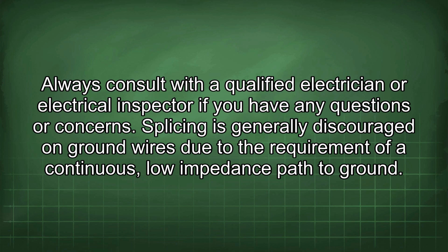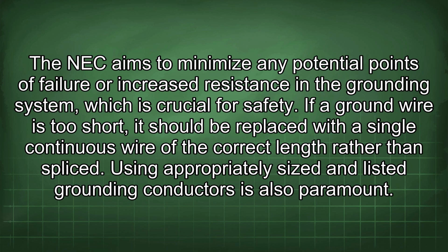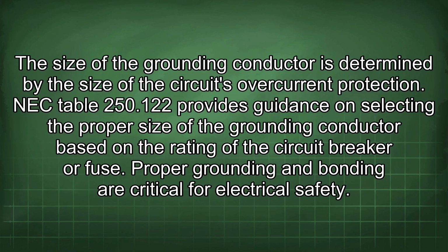Splicing is generally discouraged on ground wires due to the requirement of a continuous, low impedance path to ground. The NEC aims to minimize any potential points of failure or increased resistance in the grounding system, which is crucial for safety. If a ground wire is too short, it should be replaced with a single continuous wire of the correct length rather than spliced. Using appropriately sized and listed grounding conductors is also paramount. The size of the grounding conductor is determined by the size of the circuit's overcurrent protection.